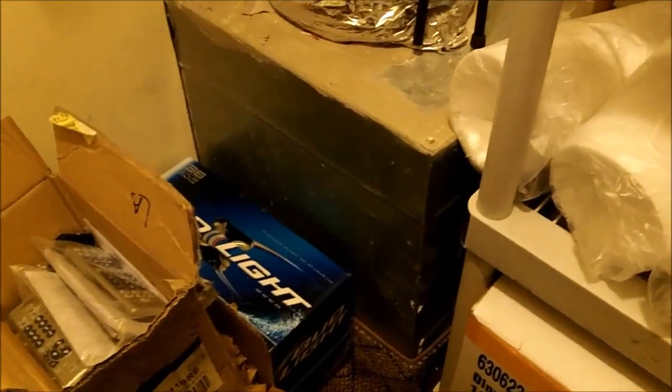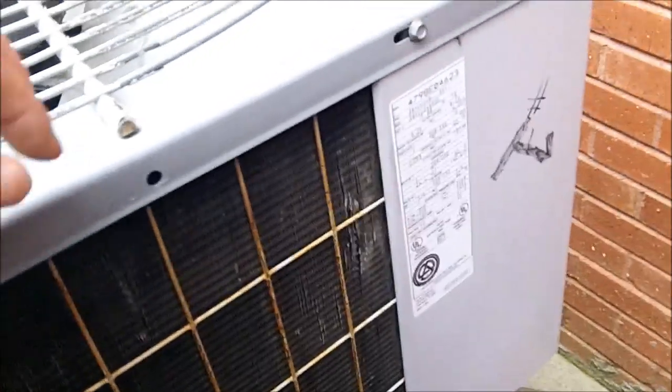Here's the back side of that three-ton with that 14 by 14 opening. There's a fresh air duct - I'm assuming that's what it is, but I've just been here a few minutes. We're going to have to add some more return air to that one, so we may have to go from the plenum up into the ceiling, across the ceiling, and into the lay-in tile.